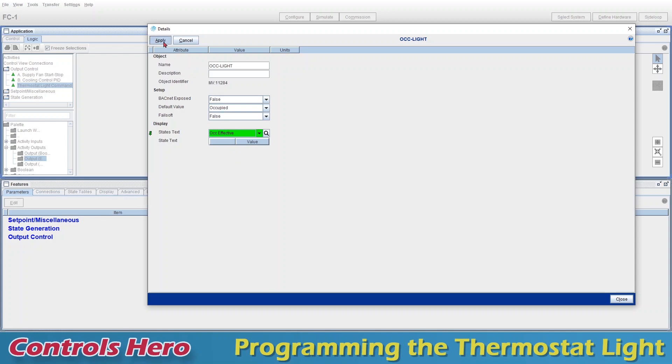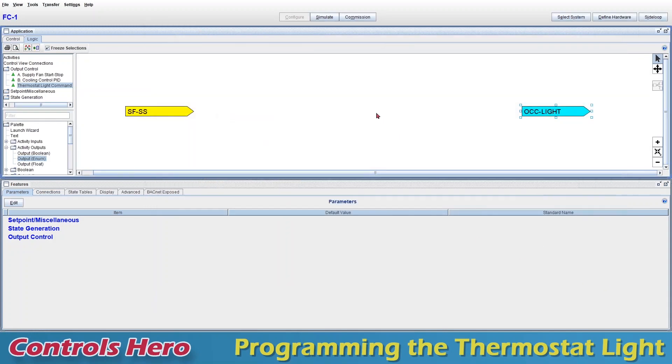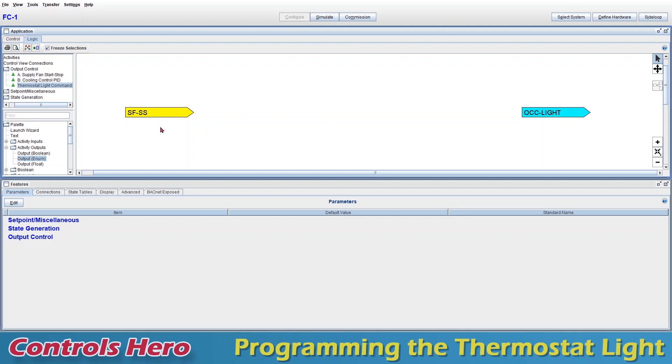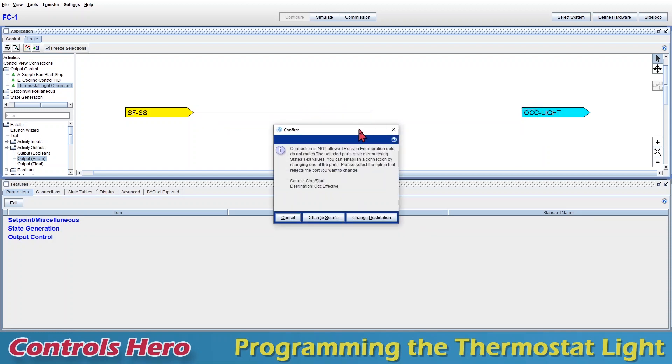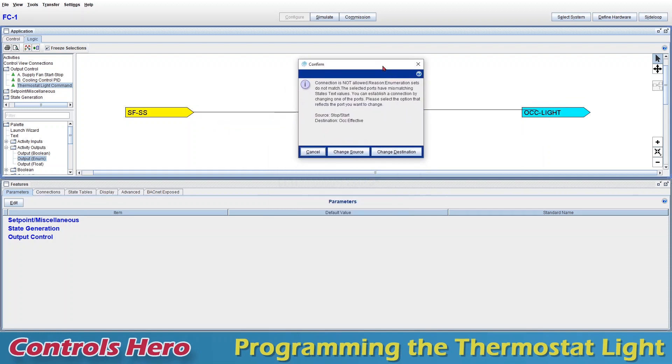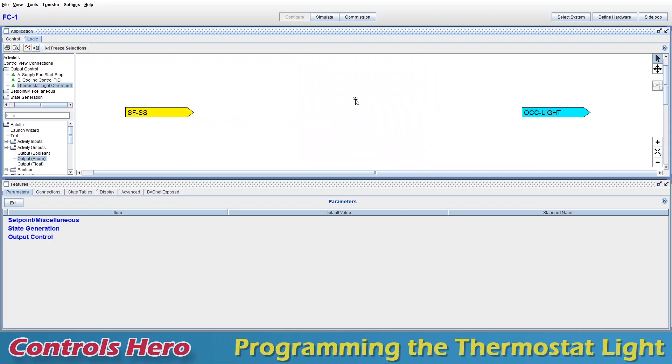Now what I want to do is to tell this output to turn on its light whenever my start stop is start and turn it off when this is stop. That simple. If I try to make a straight connection, I'll get this little window saying that the connection is not allowed. That's because my source has different units than my destination, right? Stop start and occupancy effective. We can choose to change the source or the destination so they both match, but we don't want that. So I'm just going to go ahead and cancel that and click.